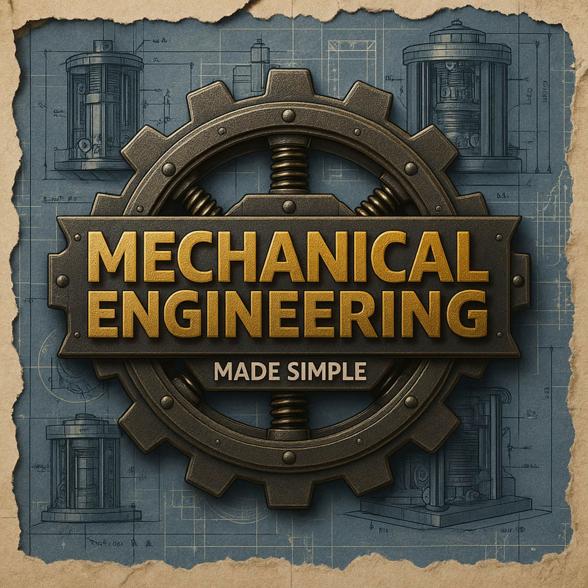Just environmental factors. Yeah, or sometimes a component has deteriorated so severely that the internal clearances have actually opened up. This temporarily reduces the impact force right before the part completely fails. Oh man, so it gets quieter right before it dies. Exactly. Any variation in amplitude, whether it goes up or goes down, demands investigation. Yeah. You cannot assume a quieter machine is a healthier machine without proving exactly why the forcing function changed.